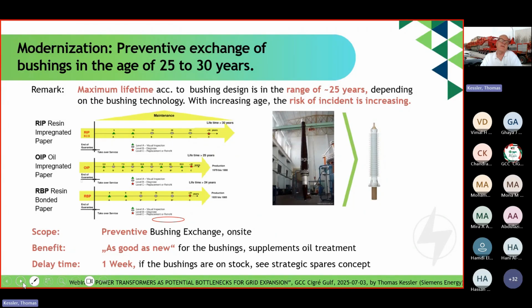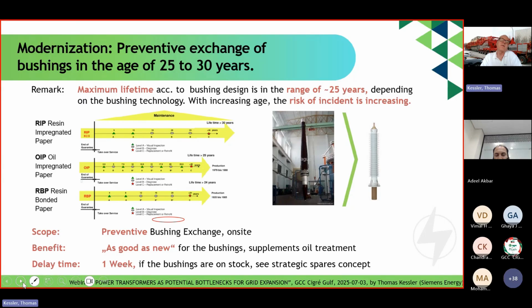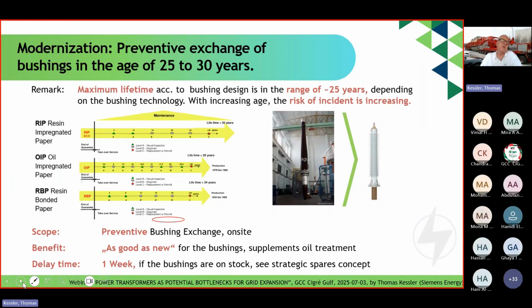So I really need to emphasize that preventive exchange of bushings, or at least inspection of bushings, is very important for the availability and lifetime extension of assets. The benefit is obvious: after that, the bushings are in as-good-as-new condition. If you have a bushing on stock, and if the exchange is carefully planned, the delay time is 1 week. Most likely you do not need to remove the transformer and install a spare unit—you can do this exercise on site if it is carefully planned and the bushings are on stock. This is why the strategic spare part concept is so important.